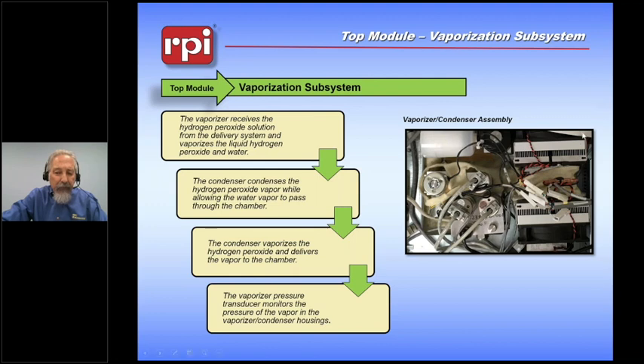there is a tray in the bottom, approximately under here, it has an opening in it, it's heated up to a very high temperature. As soon as the peroxide comes in through that piece of tubing we talked about earlier, it's immediately vaporized along with the water it contains, leaving behind any salts or preservatives that are used in the assembly of the cartridge. That vapor is then transferred into a series of metal bars that run through the middle of this condenser assembly. And these thermoelectric modules can be controlled at very specific temperatures. And we basically condense out the hydrogen peroxide away from the water, thus concentrating it.